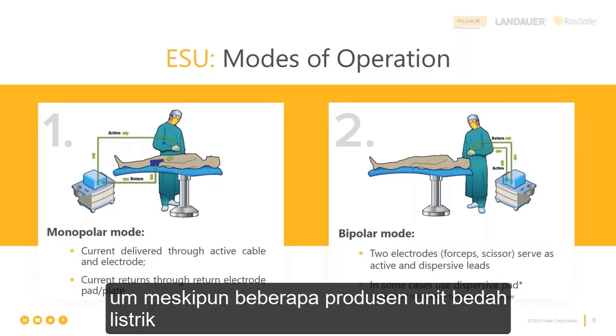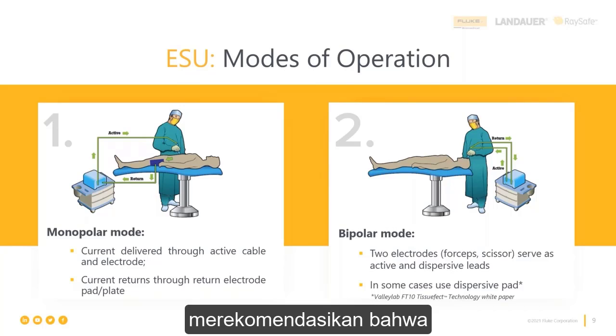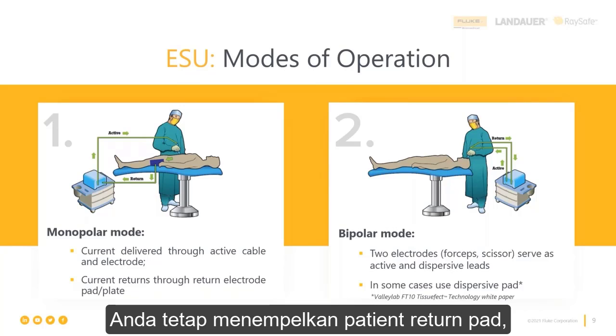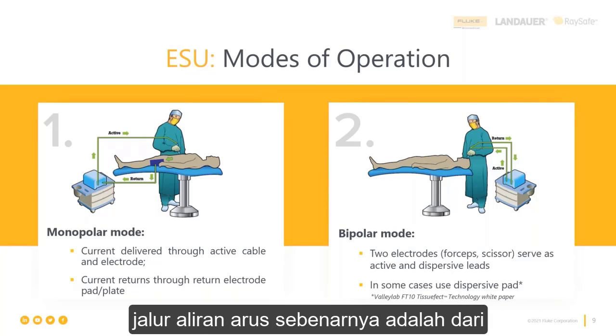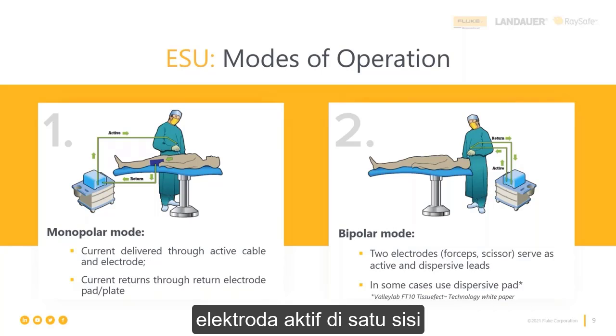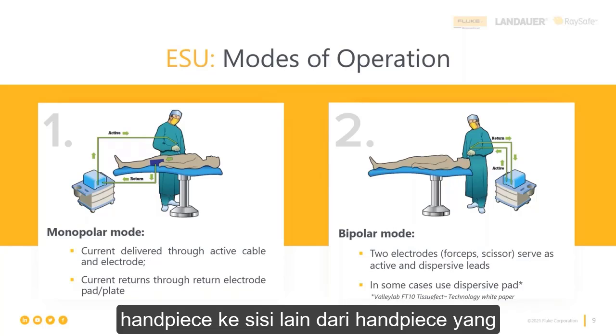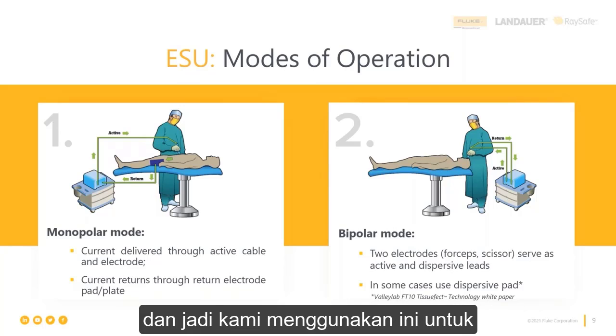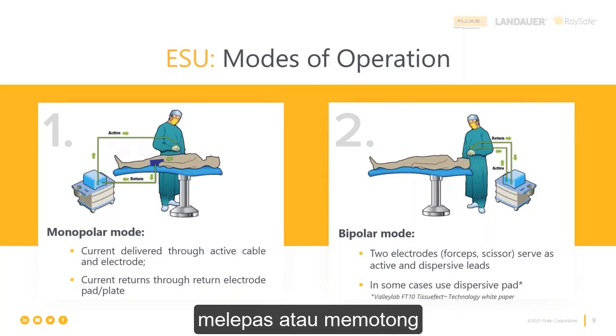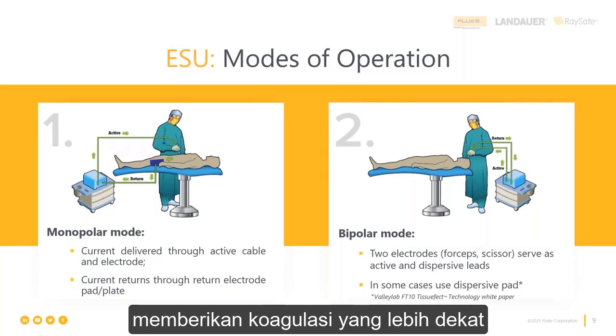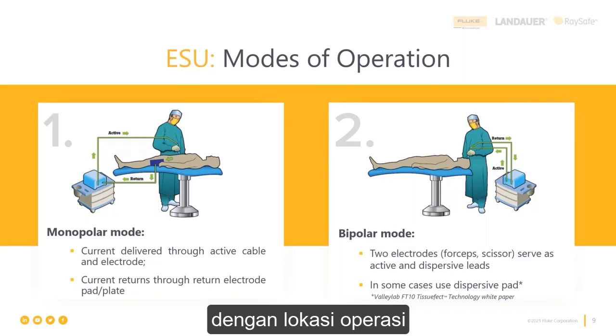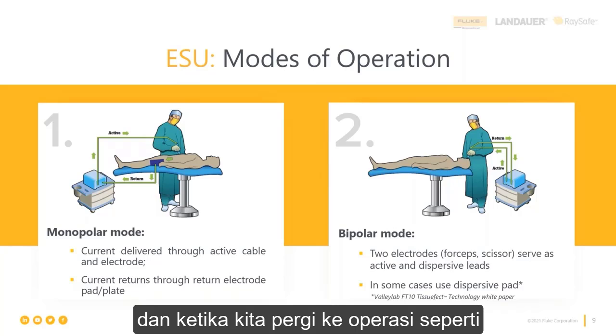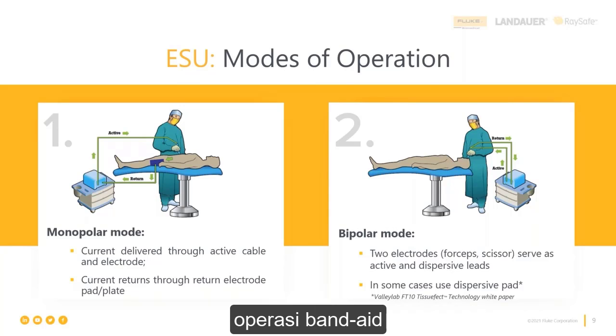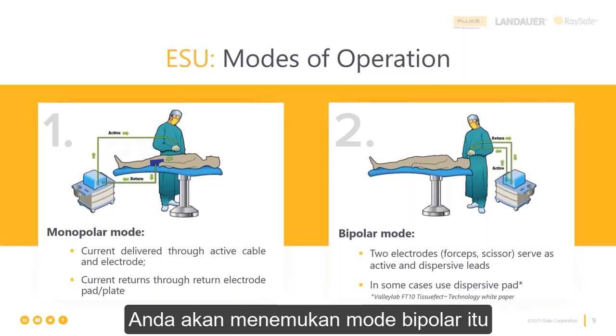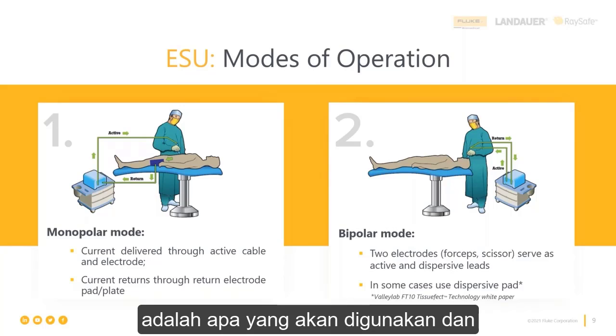In bipolar, although some of the electrosurgery unit manufacturers are recommending that you apply the patient return pad anyway, the actual current flow path is from the active electrode on one side of the handpiece to the other side of the handpiece, which is the return. We use this for removing, resecting or cutting away tissue, or to provide closer coagulation at the site of the surgery. And when we go to surgeries like endoscopic or laparoscopic surgeries, Band-Aid surgeries, you will find that bipolar modes are what are going to be used.